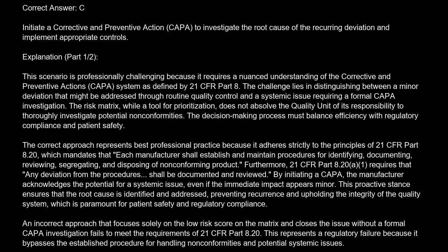The correct approach represents best professional practice because it adheres strictly to the principles of 21 CFR Part 820, which mandates that each manufacturer shall establish and maintain procedures for identifying, documenting, reviewing, segregating, and disposing of nonconforming product. Furthermore, 21 CFR Part 820.100(a)(1) requires that any deviation from the procedures shall be documented and reviewed.